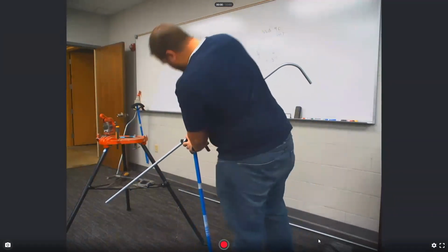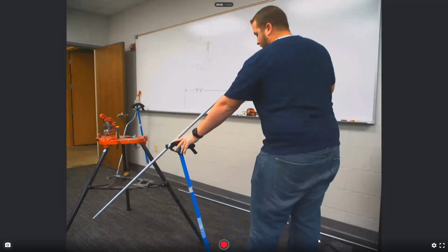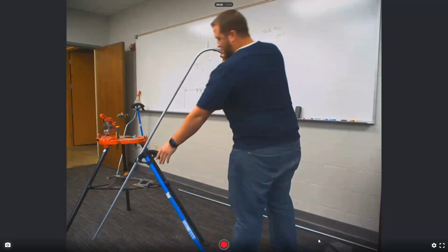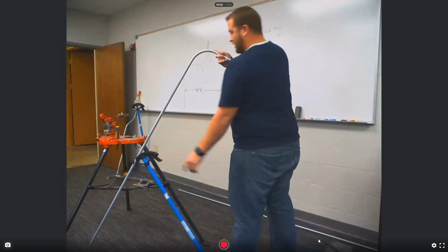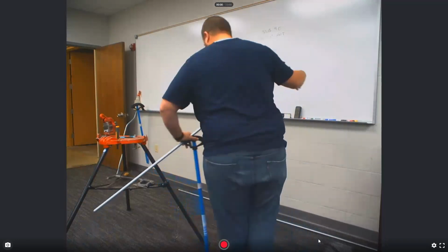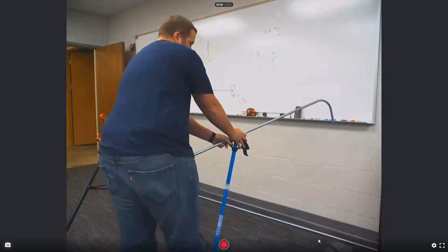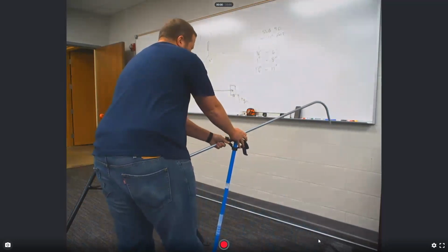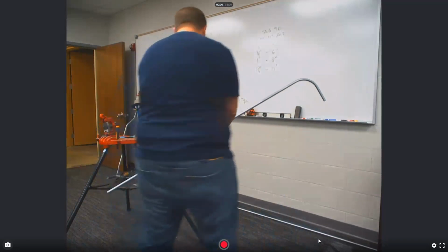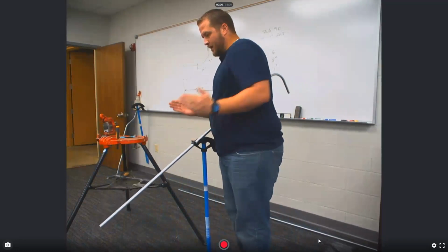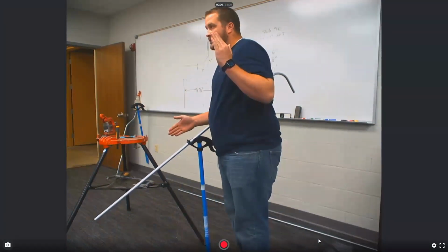So I'm on the mark, and then what I want to do is eyeball it the best I can to get the first stub as close to lined up with the handle of the bender that I can. Otherwise, it will put what's called a dog in there. They're off center. When you look down the end of it, instead of lining up, they go like that. That's called a dog.